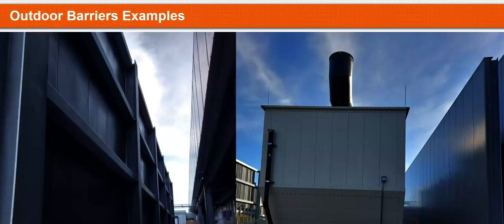These are some examples of barrier walls. They are not as simple as just putting them out there and adding on the specification. It needs to be self-supported. They're going to be exposed to wind loads. They're going to be exposed to seismic. And depending on the height of the wall, a particular wind load is going to be applied. So they come with structural requirements as well, and protection from the elements. In this case, you could see these barrier walls outside of a data center are fully powder coated with absorptive perforated metal on the side facing the source.